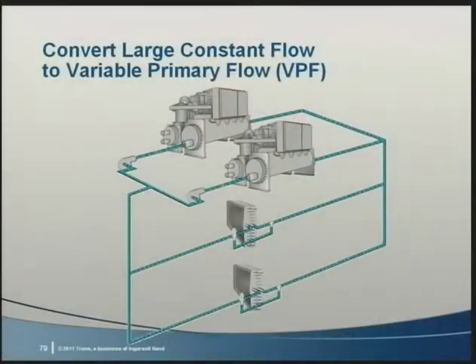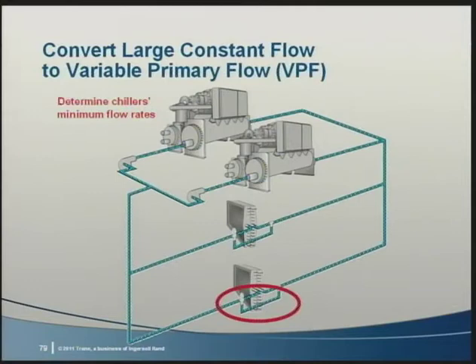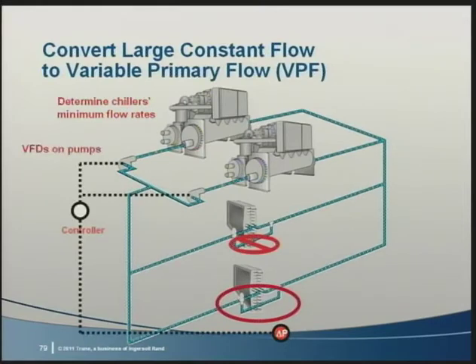Now, how about larger constant flow systems? Simply put, this is low-hanging fruit from an energy standpoint. There's a lot of money being spent to pump water through the system. Follow the same steps as for the smaller system. Determine the minimum flow rate. Find enough 3-way valves to allow it. Put a DP sensor at the most remote 3-way valves. Convert remaining valves to 2-way, and add VFDs to all pumps and control them to maintain the DP set point.